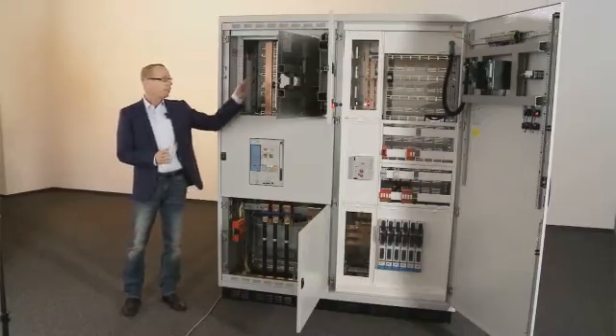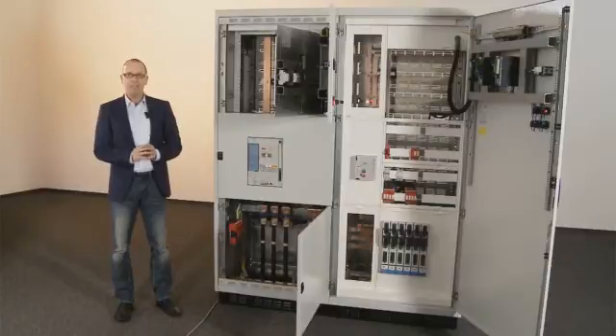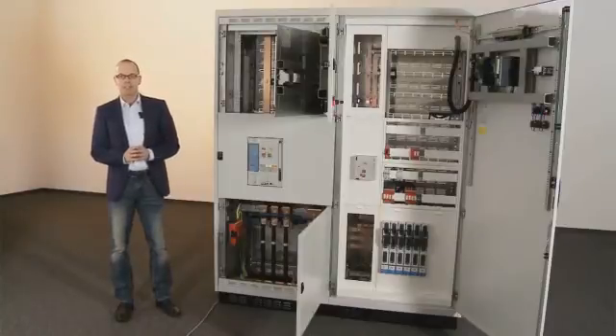The fiber optic cable used for this purpose has the advantage that no inductive coupling occurs. To sum up, Dehn Short detects an arc fault the moment it starts to develop and disconnects it. This reduces to a safe level the dangers of an arc fault for people as well as for the low voltage switchgear installation itself.